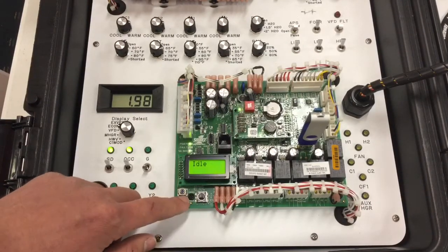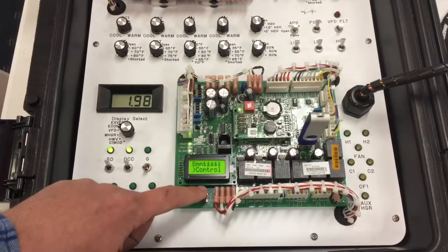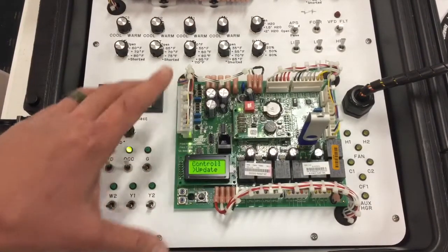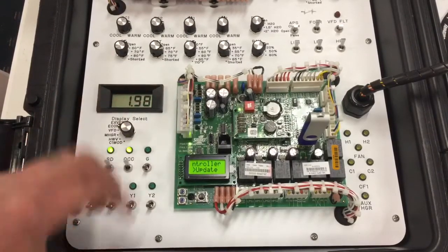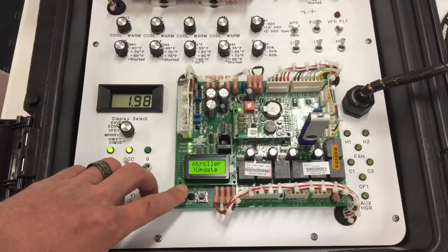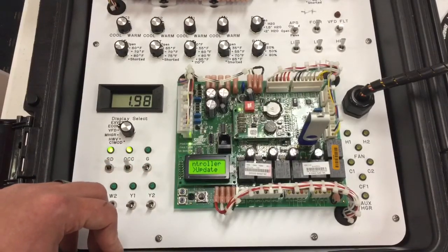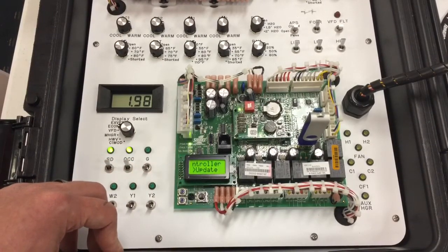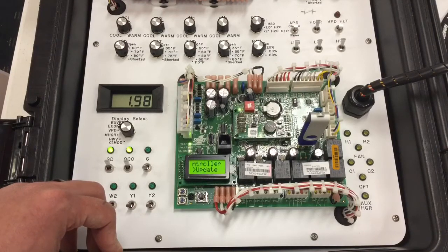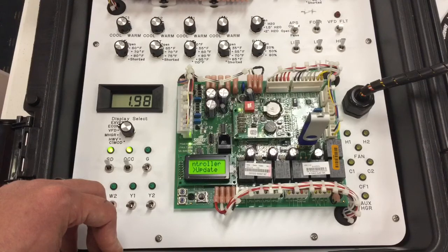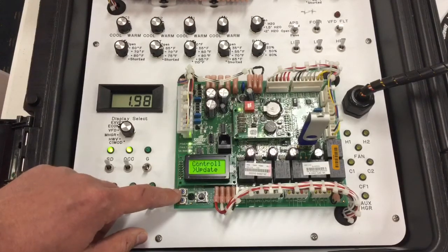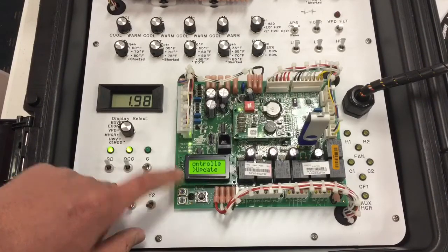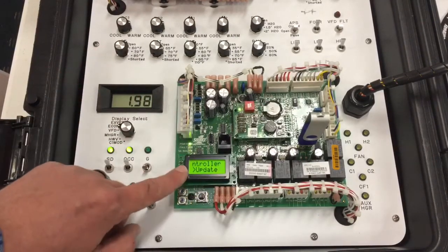At this point, I'm going to scroll back down to update. After replacing my outdoor unit control board or my main logic board of the system, I'm going to go down to update. Remember, the replacement control boards are not aware of what system they're being installed in. They're not aware of how many stages of cooling, how many stages of heating, what type of fan control is being used, nor anything else. So this will take the unit back to the way that the old board was configured.